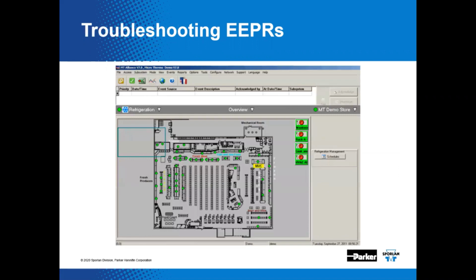Troubleshooting EEPRs. Controllers will typically allow the technician to see important control parameters and readings. When integrated with the EMS, that's the energy management system, these readings can be graphed and viewed as time varies. The EMS would also show any alarm warnings if set points are not being met. And again, these systems are intended to be monitored remotely. You can't do that with a mechanical EPR. Let's now take a look at this next slide.